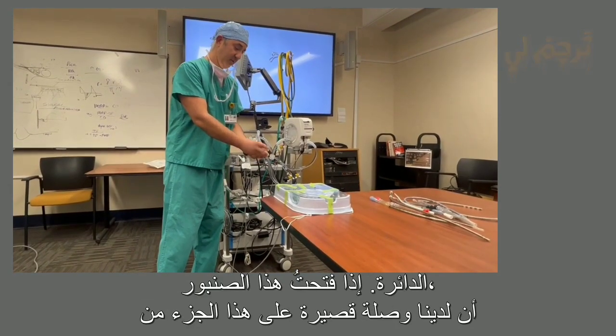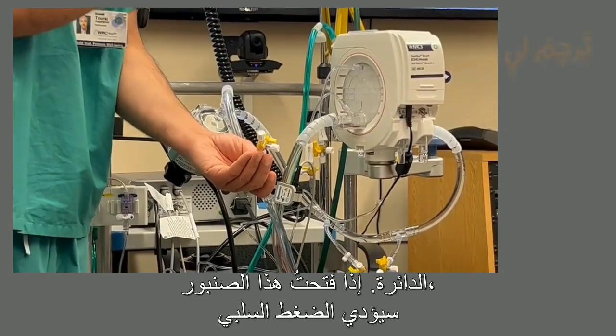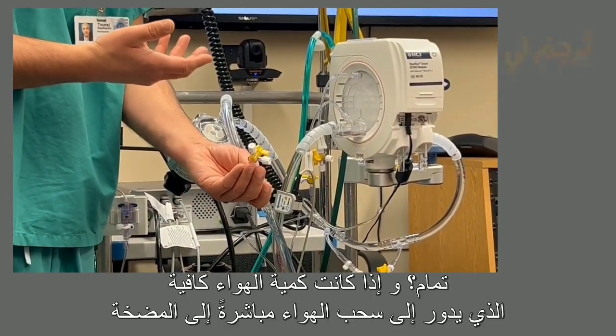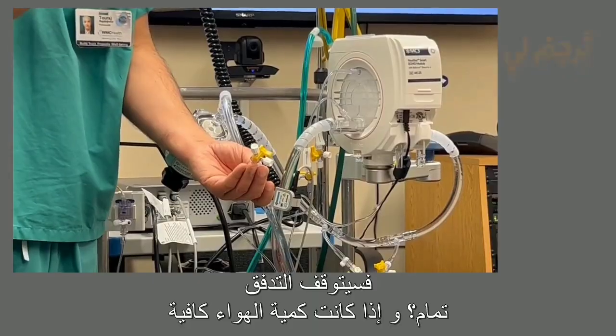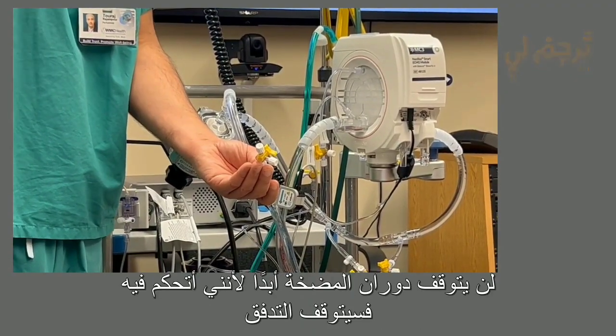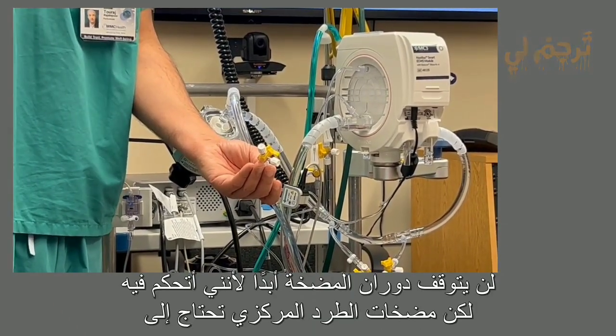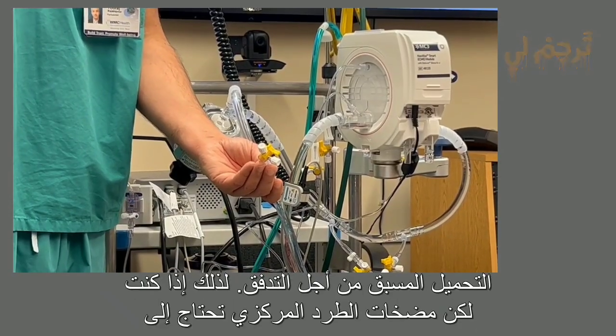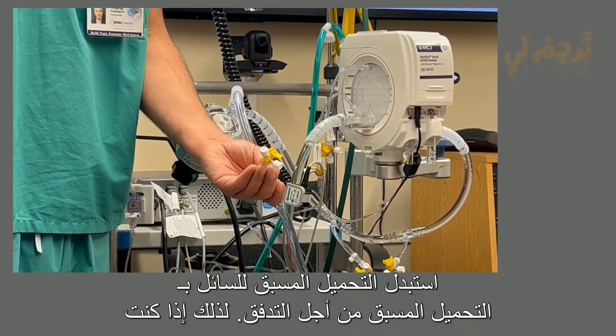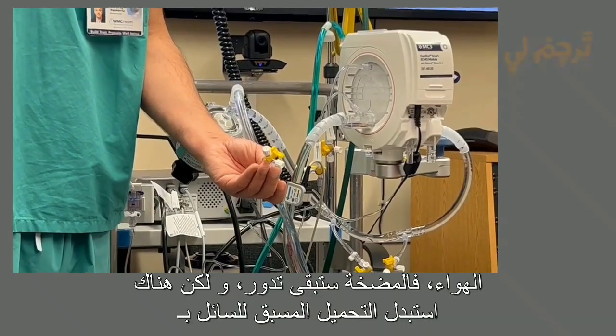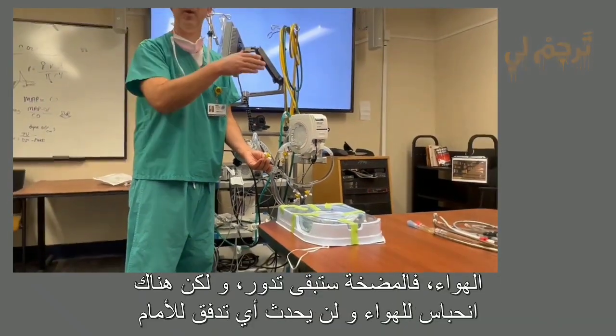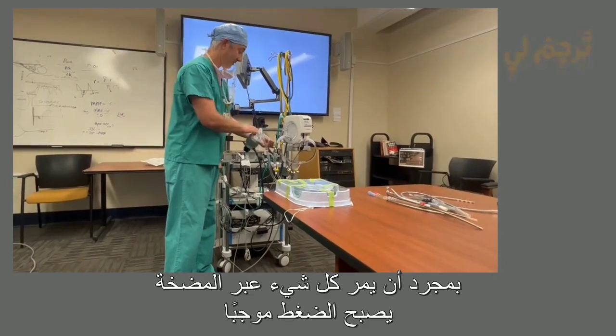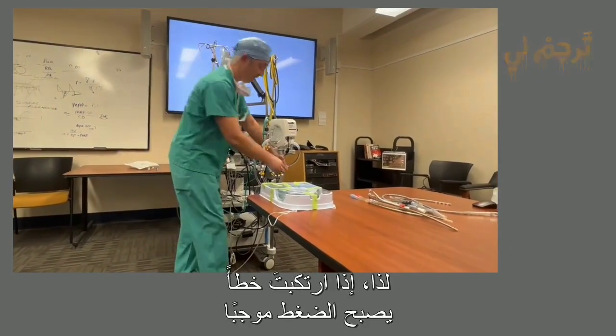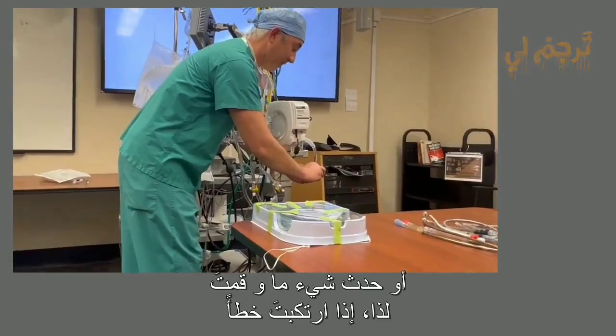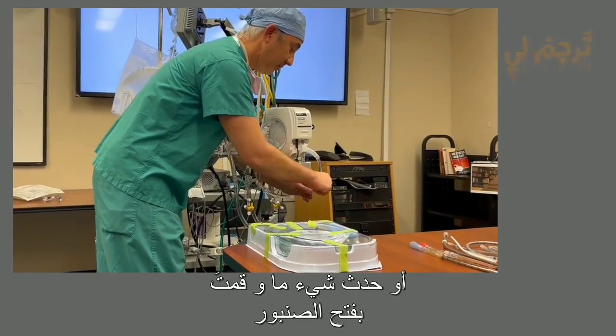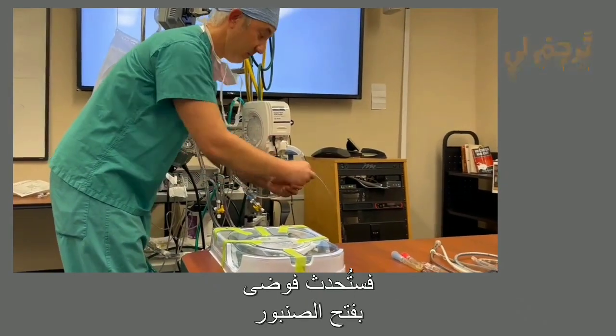If I was to open this stopcock, that negative pressure from the spinning would suck air right into the pump, okay? And if it's enough air, it's going to stop flow. It will never stop the pump from spinning, because I control that, but centrifugal pumps need a preload in order to flow. So if I replace the preload of fluid with air, the pump still spins, but there's an airlock and no forward flow will happen with the blood. Once everything gets past the pump, it's all positive pressure. So if you were to make a mistake, or something happened and you opened up the stopcock, you're just going to make a mess.